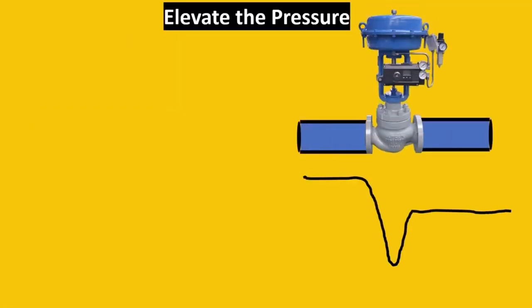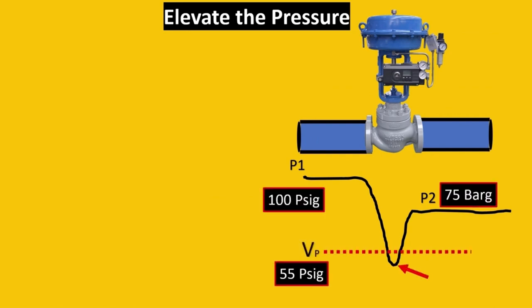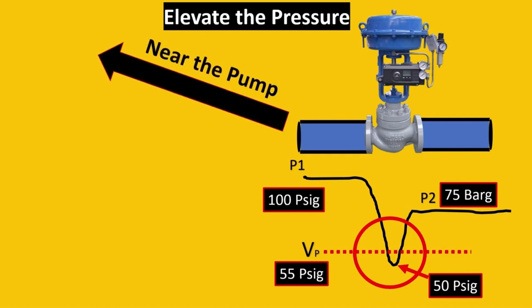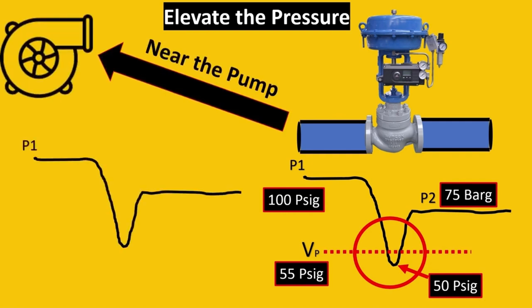Here's your control valve and the pressure drop curve. Your vapor pressure shows cavitation will happen because the pressure drop goes beyond 50 psig and vapor pressure is 55 psig. What we do is move this entire solution near to the pump and see what happens. When near the pump, the same pressure drop curve occurs but P1 is now elevated by 10 psig.